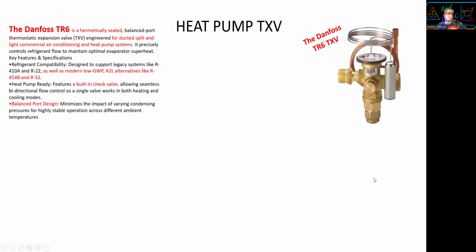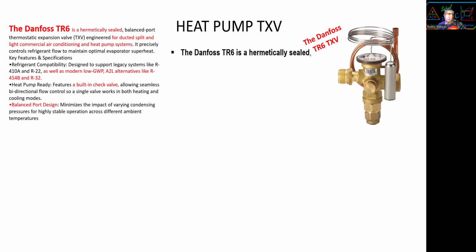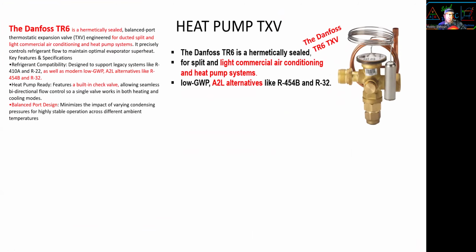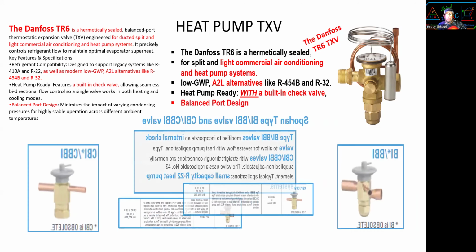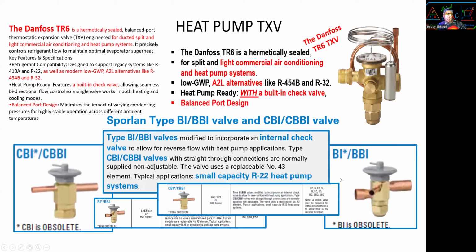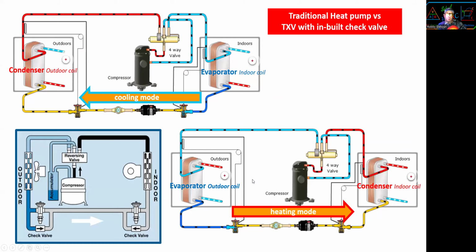Now let's talk about heat pump TXVs. We have different TXVs for different styles. The heat pump TXV, the Danfoss TR6, is for light commercial air conditioning and heat pump systems. It's designed for the new A2L alternative refrigerants, and it has a built-in check valve. That's why it's a heat pump valve, and it's a balanced port design. And this is the Sporlan version of it. Traditional heat pump versus TXV with a built-in check valve.